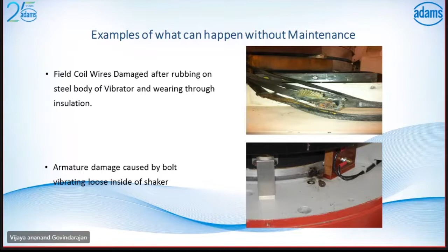The second one, there is a loose connection in the bolt, and it is dropped inside the armature. Sometimes a dust cover which is damaged may allow external components inside the shaker. If there is any mistake while mounting the fixture, or an accidental drop of bolts, and the dust seal is not maintained properly, then that bolt may go inside. Even a very small bolt can cause severe damage to the armature. That is what is seen in the second image.